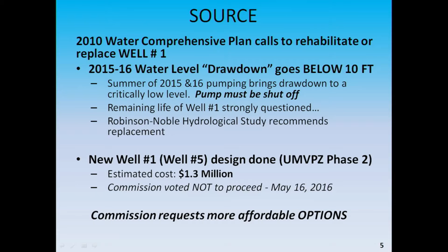Looking again at well 1 before we get into the options: well 1 is our number one well. It has the calculated capacity, and if we run it at maximum, when it was new, it would put out about 1,500 gallons per minute. As I mentioned, we only operate it currently at about 1,100. Without that well online and functioning, we may have to limit development, depending on what the health department allows us to move forward with. We may have to do some kind of conservation, be it water rationing or alternate day watering, to reserve and allow the storage tanks to fill back up. There are obviously fire flow concerns without well 1 in operation, and we also have no backup or redundancy for wells 3 or 4. So it's a pretty fundamental key piece of our water utility.